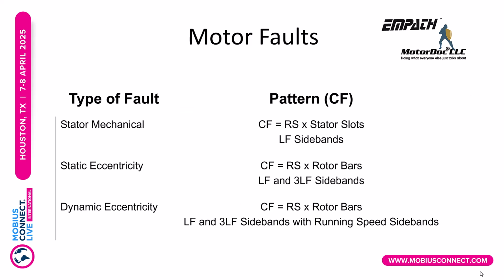So some of the motor faults we're going to look for. Stator mechanical, the running speed times stator slots with the line frequency sidebands is what we're going to see. It's an amplitude modulated signal, so we're not going to see the primary calculation like we would expect to see in vibration. We're just going to see sidebands.